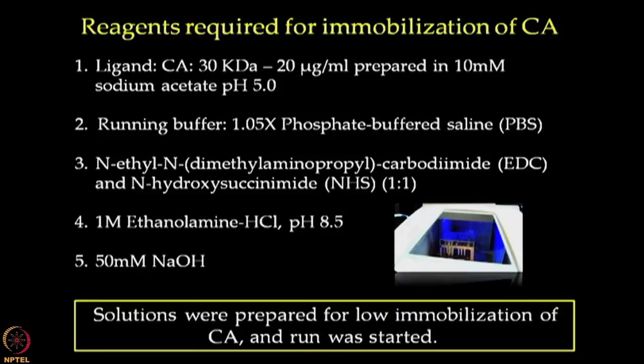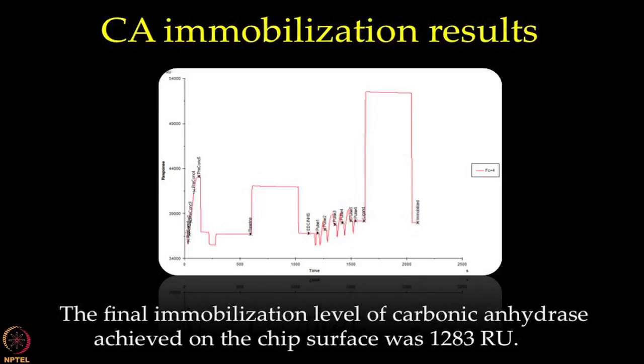After preparation of these samples and reagents, we transfer the sample tubes to the appropriate rack and start the run as shown for beta 2 microglobulin immobilization in earlier lectures. We will hence look at the immobilization results obtained from this run. Since it is recommended to use lower immobilization levels for kinetics assay compared to screening assays, we targeted an immobilization level of 1500 RU for carbonic anhydrase. As shown in the figure, the immobilization procedure resulted in final immobilization level of 1283 RUs.